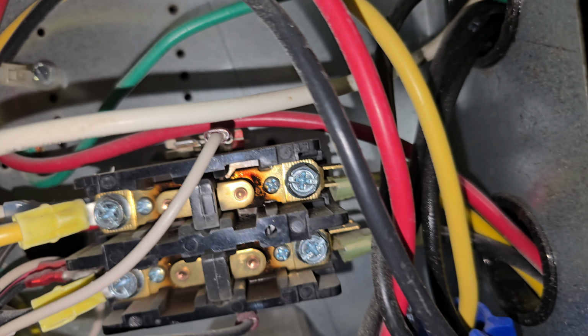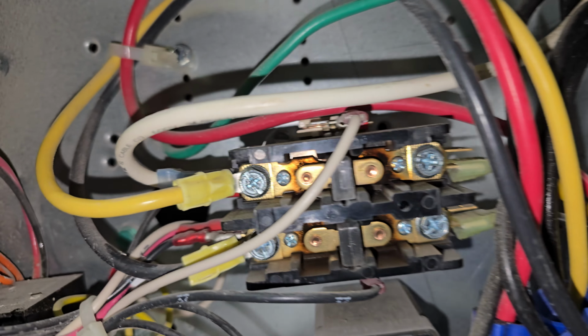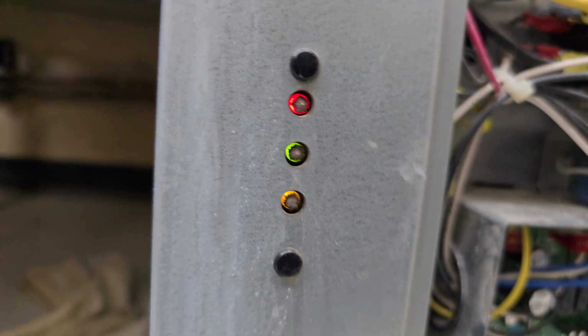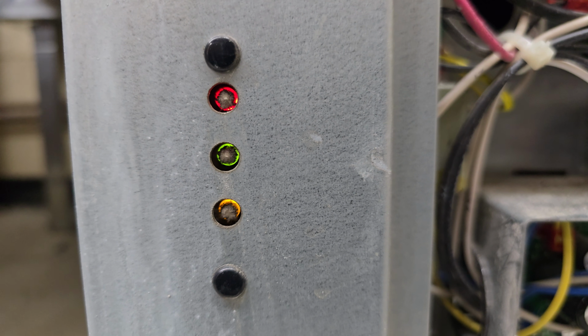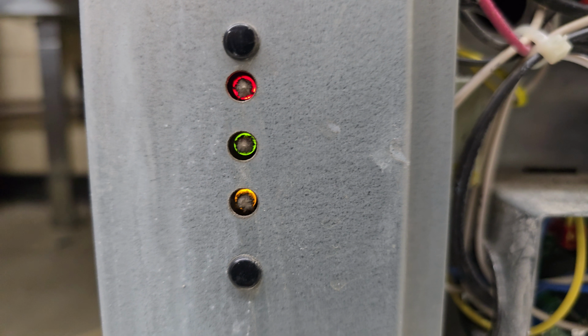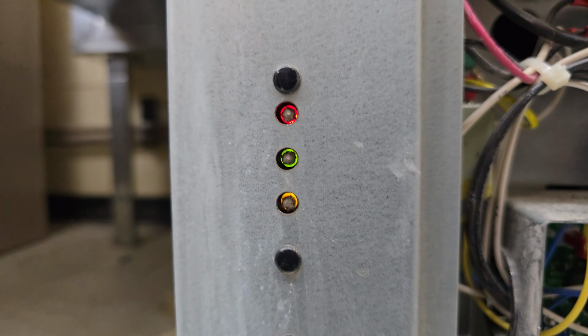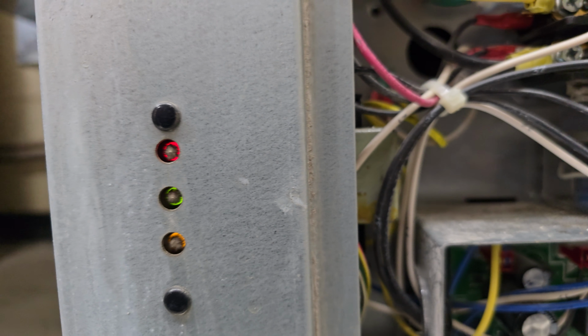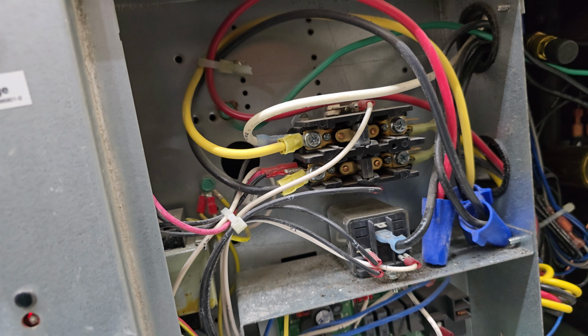Okay, though the contactor coil is energized, the contactor is burnt out. You can see my compressor is in there. So this unit has a flash code, and I'm gonna see what's going on with it. You see it has green and yellow flashing at the same time with the red light on. So we'll see what the flash code says.